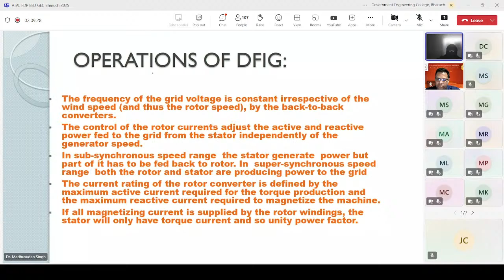Now the control of the rotor side converter, grid side converters, again there rotor side has to do two tasks, rather three tasks. The first is that control of torque and flux of the machine through rotor current, active and reactive power flow of the machine through rotor current, and if there is a requirement of MPPT also need to be implemented through RSC. GSC has a major requirement, grid side converter, that is what is shown here. You see this one, the rightmost.